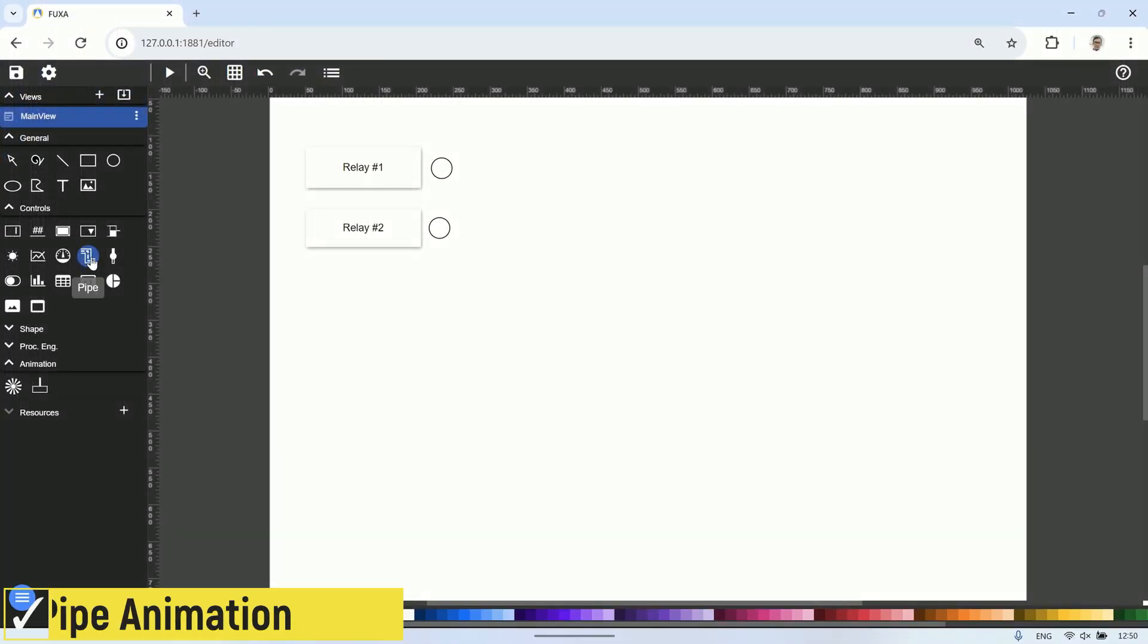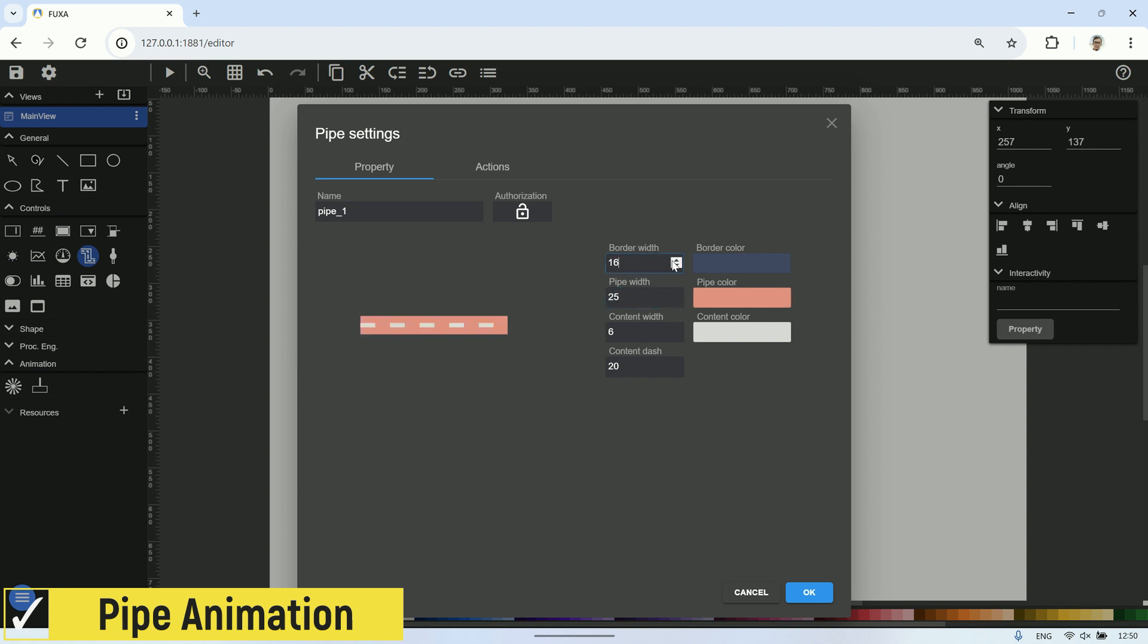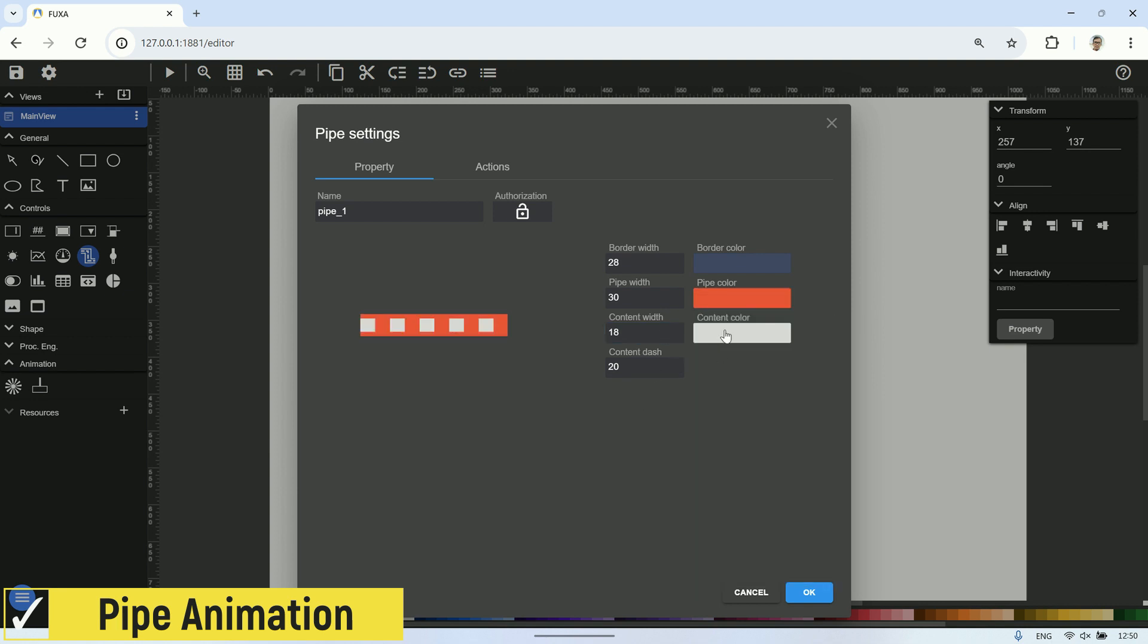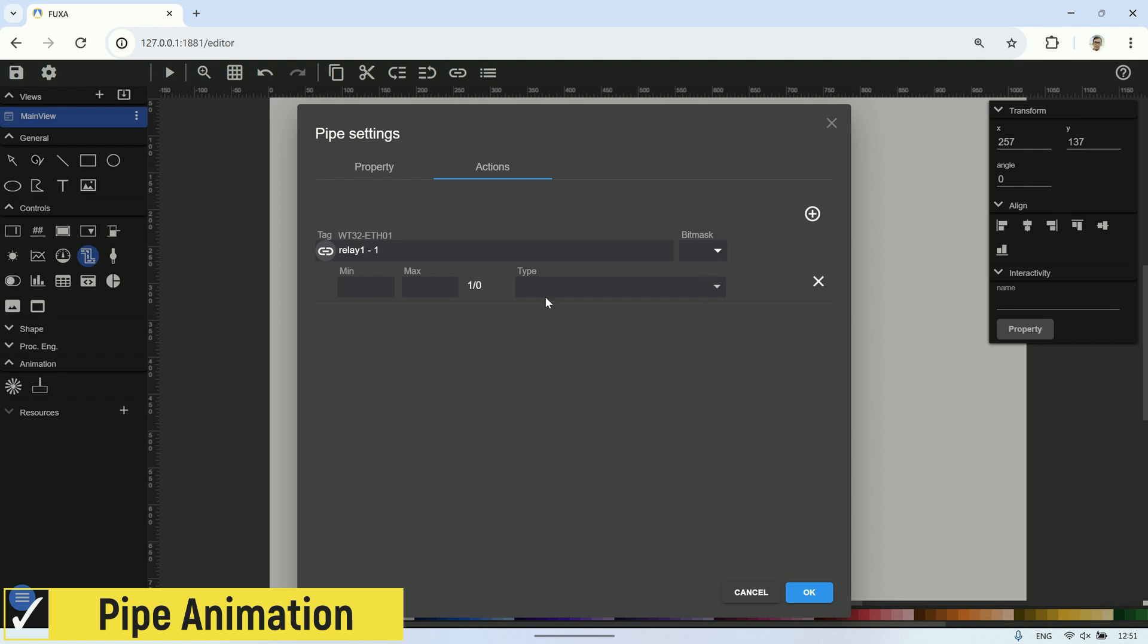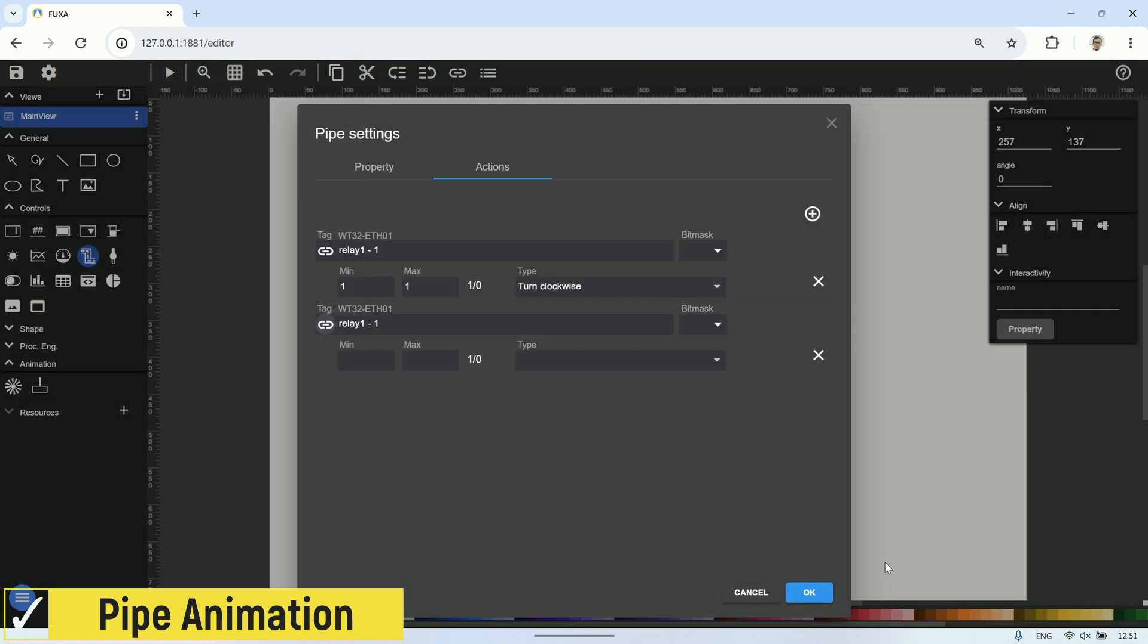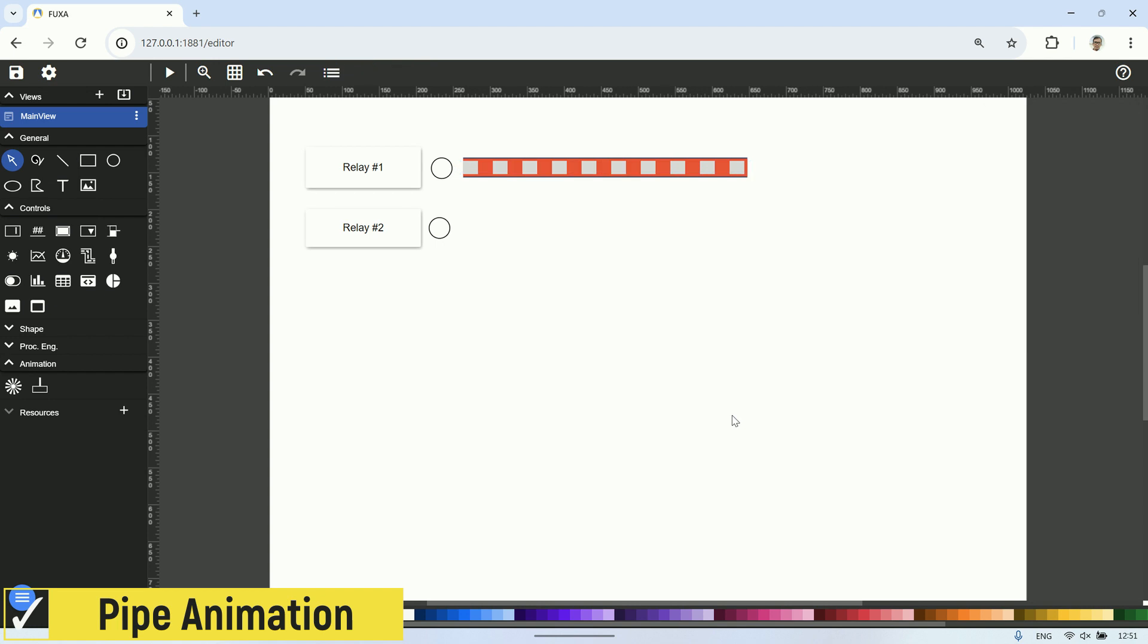Next, let's try the pipe animation. Click on the pipe tool and draw a line representing the desired pipe flow. Then, in the pipe settings, choose the desired properties such as border size, pipe width, content width, content dash, and its color. Next, in the action tab, bind the tag to relay one. Set min and max to one, meaning for a value of one or true in relay, choose turn clockwise as the type. Add a condition for when the relay one status is zero or false. Set min and max to zero and choose stop as the type. Once done, test if the visual works when the relay is on and stops when the relay is off.